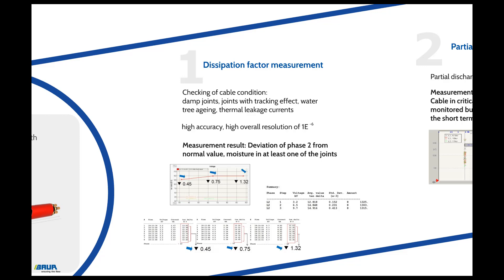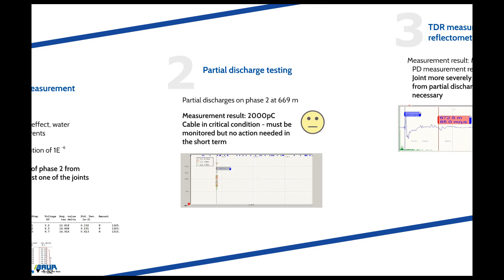A high level of accuracy and an overall resolution of 1×10⁻⁶ are necessary for the identification of damp joints. In our example, the dissipation factor measurement shows a deviation of phase 2 from the normal value, which leads to the conclusion that there is moisture in at least one of the joints. The subsequently performed partial discharge testing identifies partial discharges on phase 2 after a length of 669 m. The partial discharge level of 2000 pC leads to the conclusion that the cable is in a critical condition, but the results of the partial discharge testing do not necessitate immediate action.